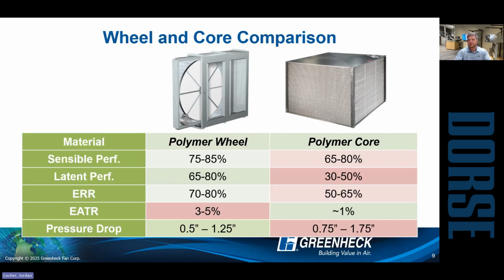Comparing wheels to cores, right? So there are some differences in the technology. If we talk high level, right, the big draw to a core is, hey, it's simple, no moving parts or pieces, right? That's always kind of been the appeal to that. But with that being said, there are some significant drawbacks as well, right? So if we take a look at performance, you can see that wheels are going to win out on both sensible and latent performance. Sensibly, cores can do okay. Latent is really where the drastic difference is, right? So you can see that difference between 65 to 80% latent recovery on a wheel, closer to 30 to 50% latent recovery on a core.